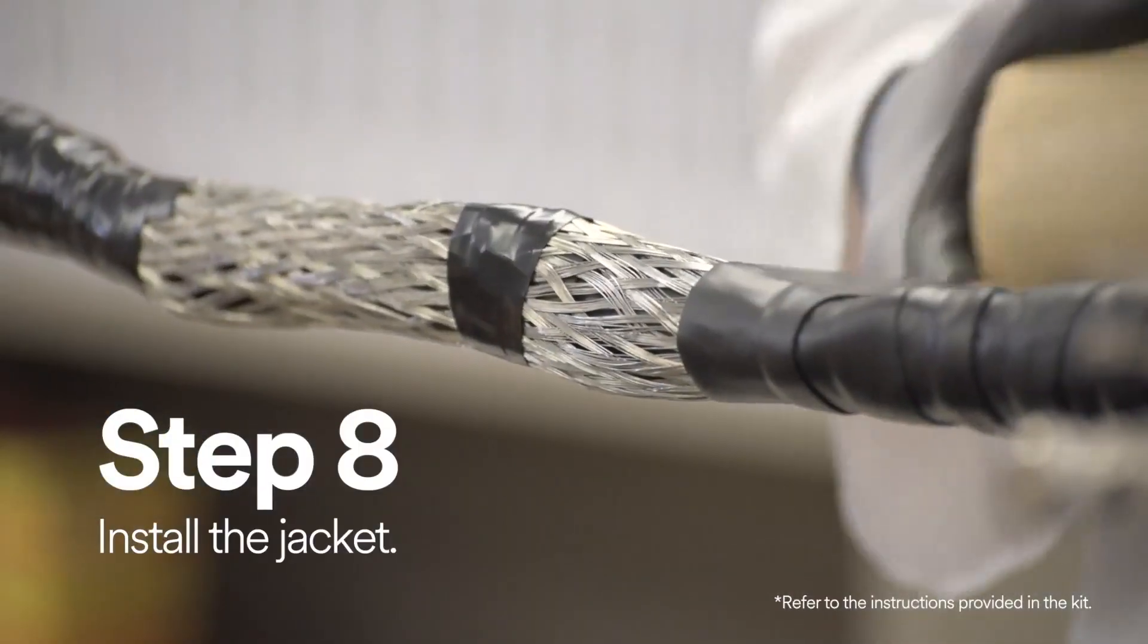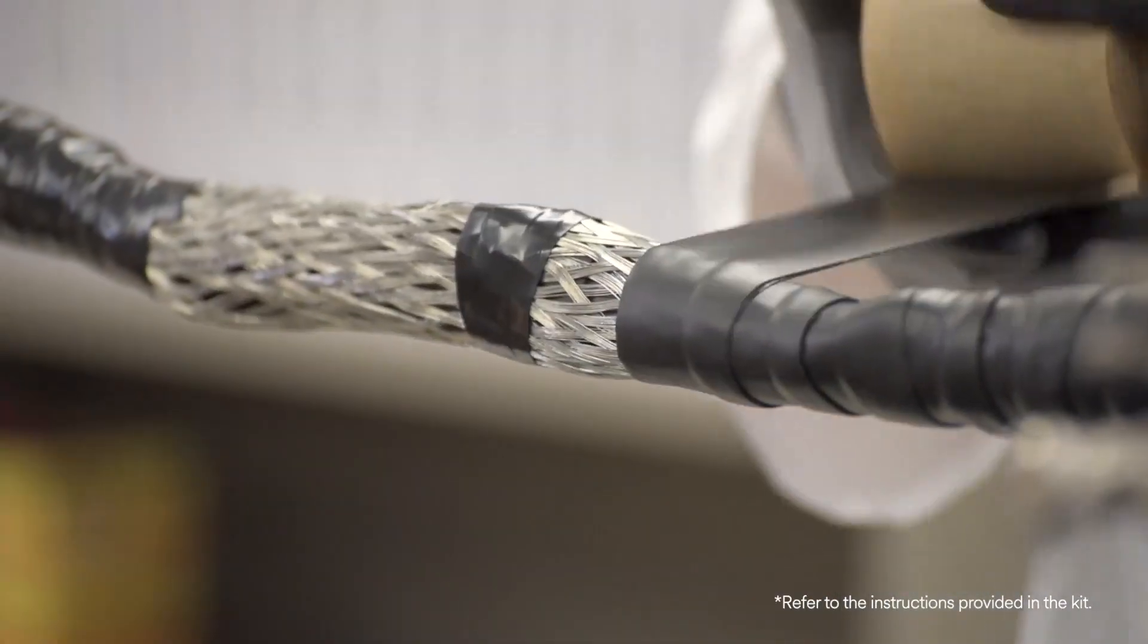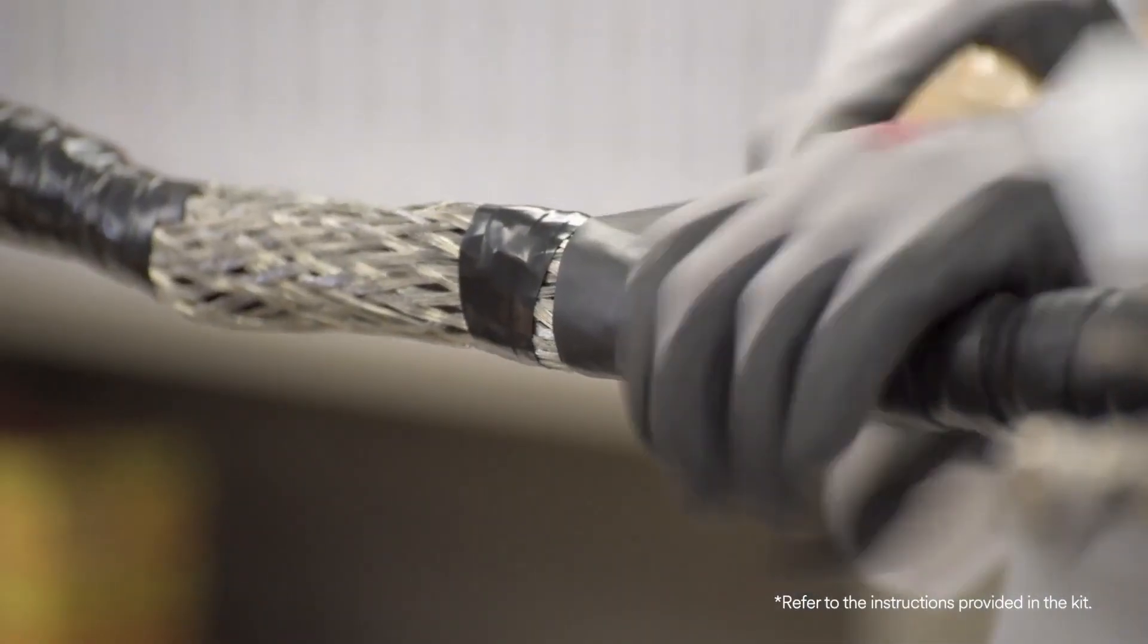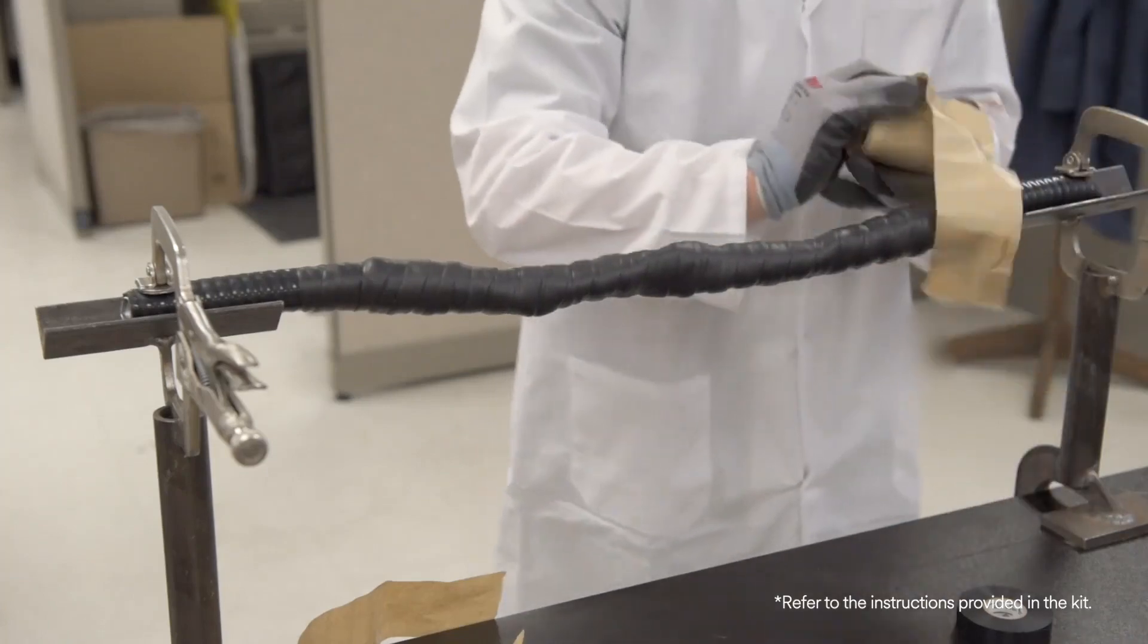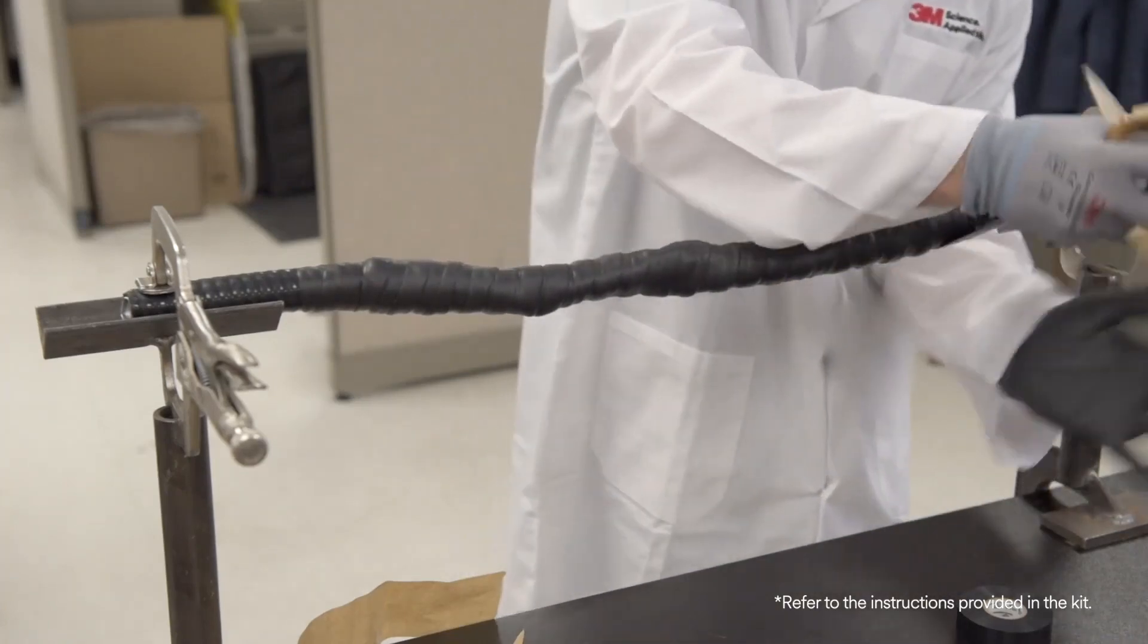At both ends of the splice, apply two half-lapped layers of scotch rubber mastic tape 2228 around the cable jacket, making sure the tape extends 2 inches over the jacket.